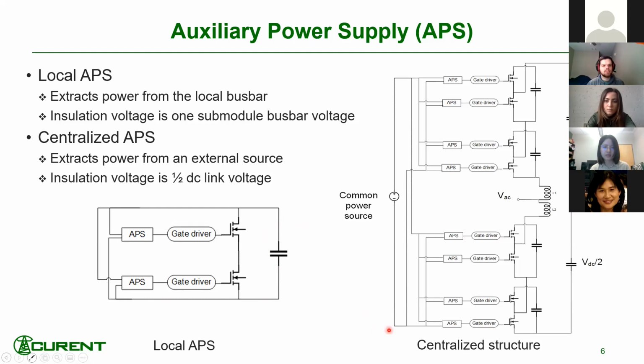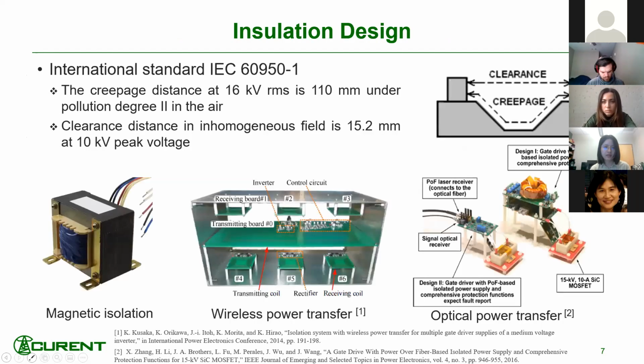Another type is the centralized structure, which means the APS would extract power from an external source instead of directly from the submodule bus, but this would increase the insulation voltage to 1/2 of the DC link voltage. So the insulation voltage is increased. And to tackle this insulation issue, we try to follow the international standards to do the insulation design.